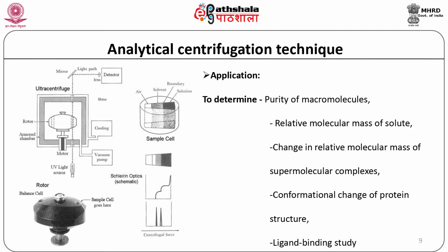Analytical centrifuge is capable of speeds approaching 70,000 revolutions per minute and it spins the rotor at an accurately controlled speed and temperature. It is evacuated, provided with a protective chamber, refrigeration and optical system to observe sedimenting material throughout the duration of centrifugation. In this method, the concentration distribution of the sample is determined at known times using absorbance measurements.